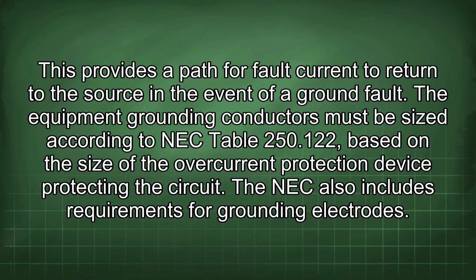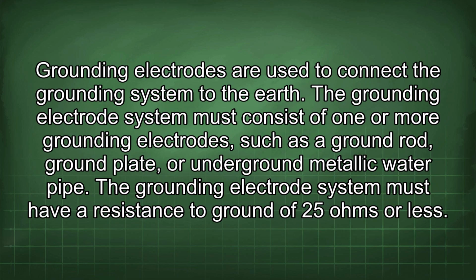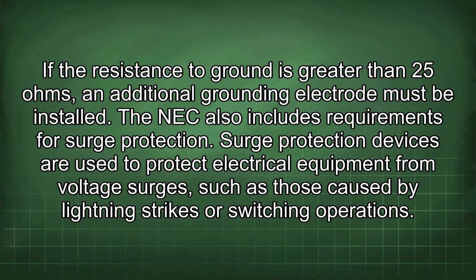The NEC also includes requirements for grounding electrodes. Grounding electrodes are used to connect the grounding system to the earth. The grounding electrode system must consist of one or more grounding electrodes, such as a ground rod, ground plate, or underground metallic water pipe. The grounding electrode system must have a resistance to ground of 25 ohms or less. If the resistance to ground is greater than 25 ohms, an additional grounding electrode must be installed.